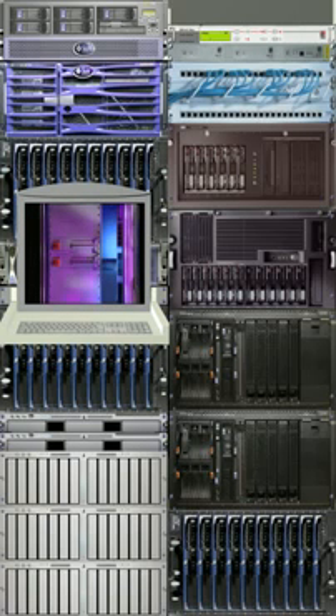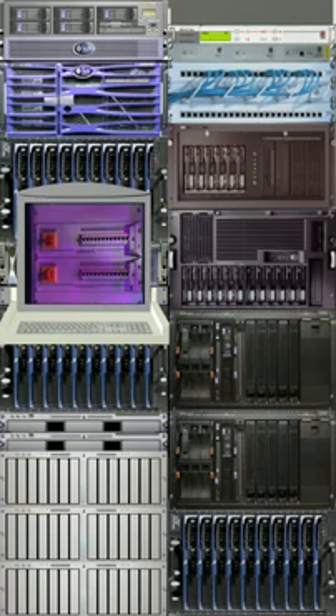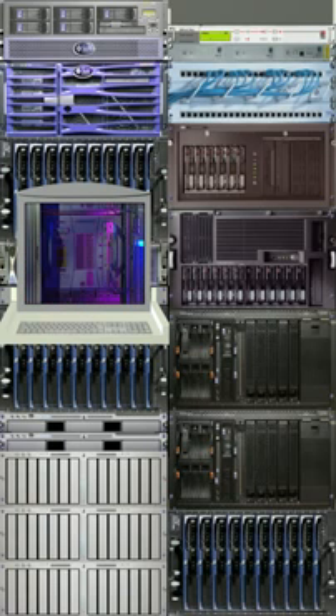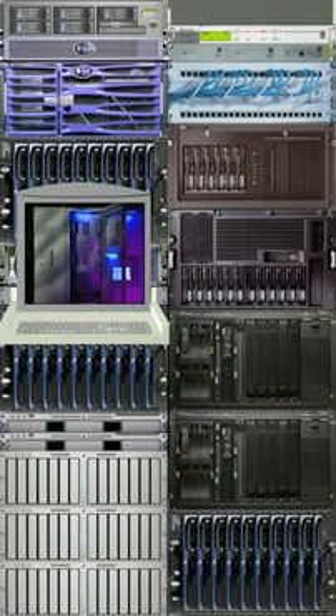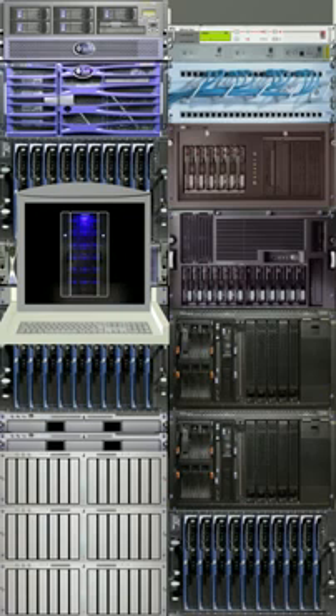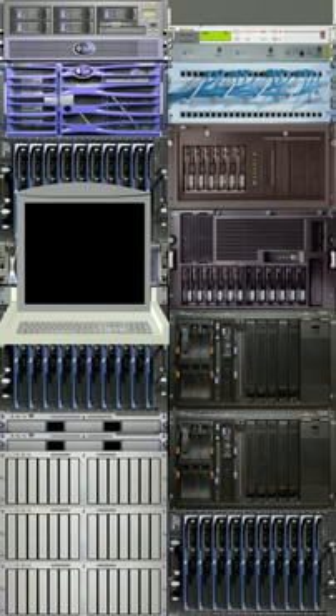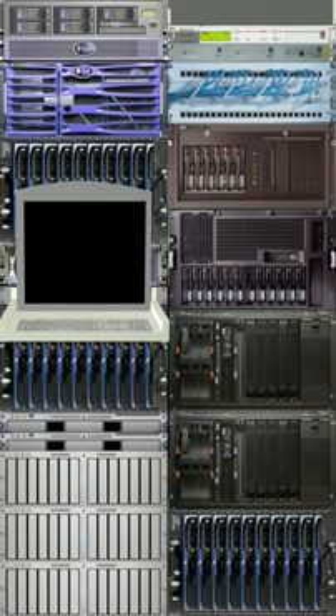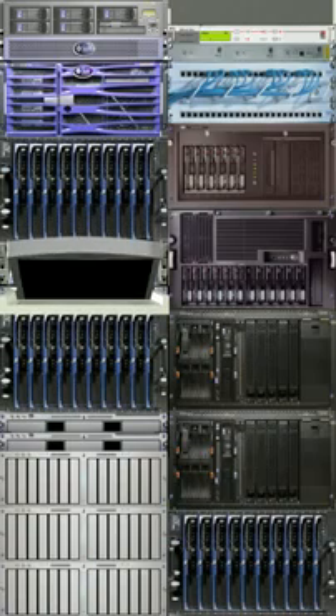On the power side, each server now typically has dual redundant power feeds, and in turn, each feed is supported by a UPS that may have its own redundancy UPS or backup generator supply. Even the thermal aspect of data center design is covered by N+1 redundancy. All of these really only protect uptime and data though. What happens if you have a fire?